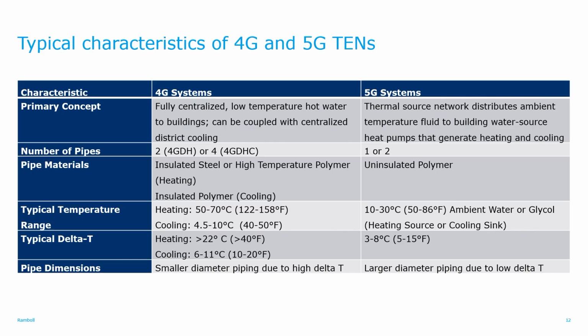I put some temperature ranges down here. These are not set in stone, just trying to be indicative. There's certainly some that are outside of those ranges as well. Note the delta T is the difference between the supply temperature and the return temperature, and the larger that is, the more thermal energy can be carried in a given pipe. For 4G systems, they do have a larger delta T, which can accommodate smaller pipe diameters as compared to 5G systems with lower delta T.